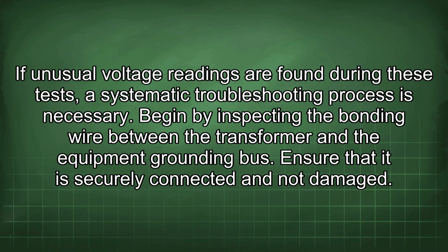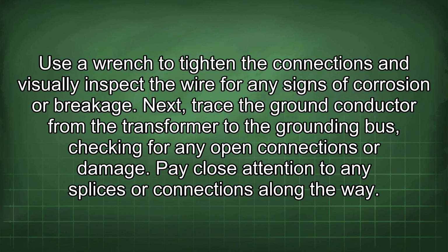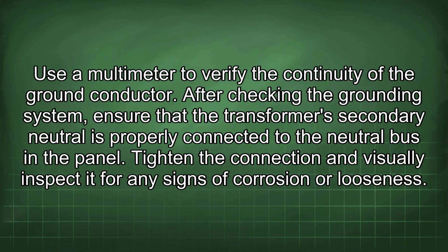Begin by inspecting the bonding wire between the transformer and the equipment grounding bus. Ensure that it is securely connected and not damaged. Use a wrench to tighten the connections and visually inspect the wire for any signs of corrosion or breakage. Next, trace the ground conductor from the transformer to the grounding bus, checking for any open connections or damage. Pay close attention to any splices or connections along the way. Use a multimeter to verify the continuity of the ground conductor.